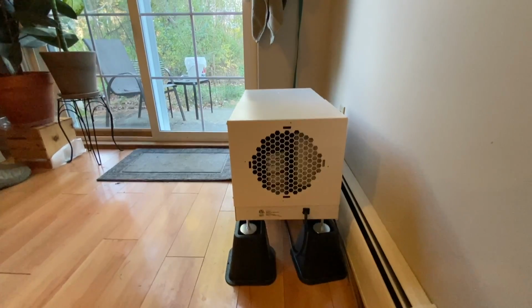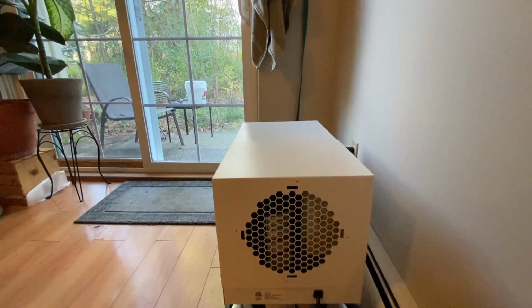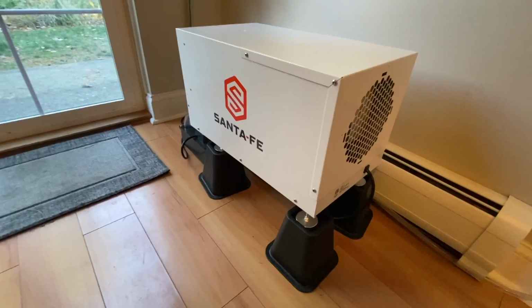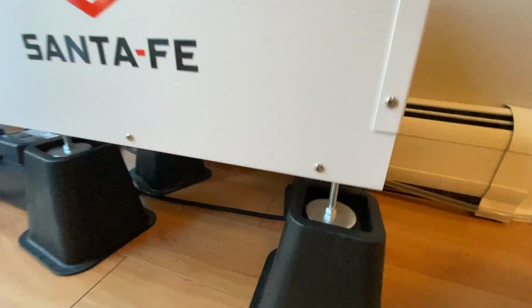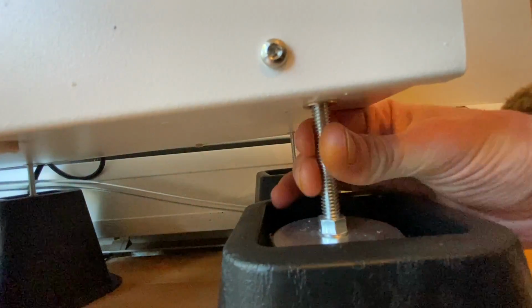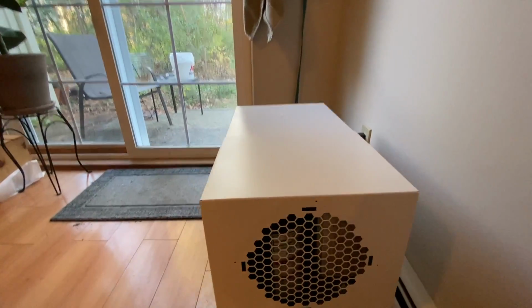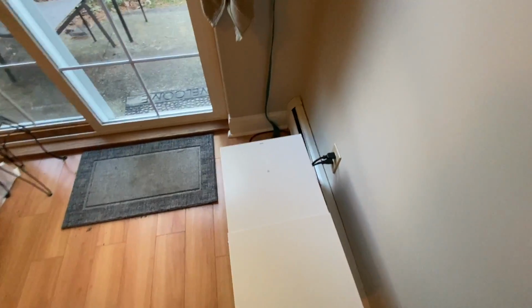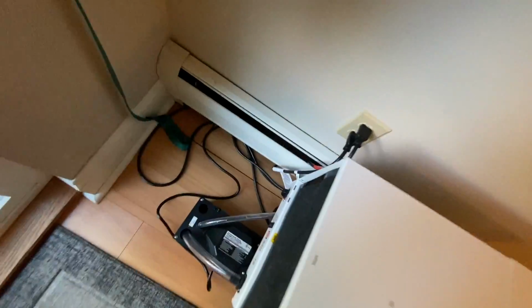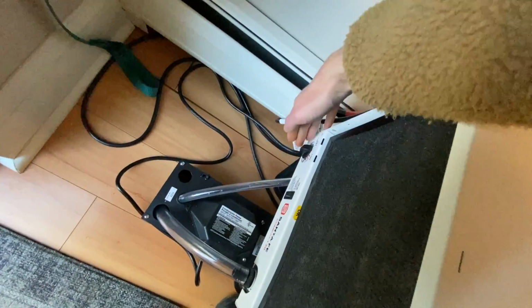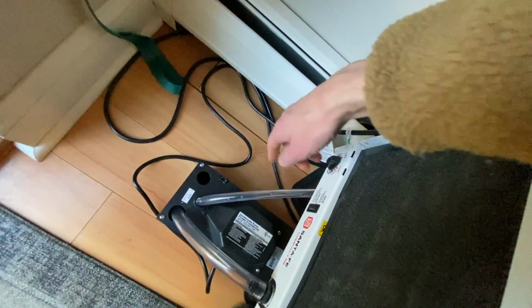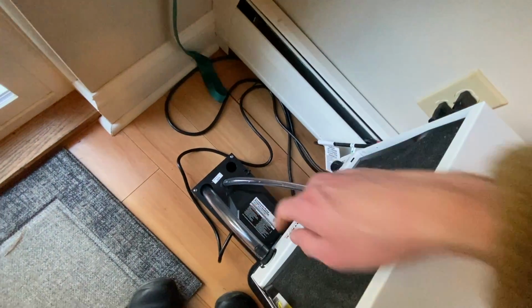After you've situated it on risers, what you're going to do then is level it. And the way that you're going to accomplish leveling it is you're going to be tightening or loosening these legs. So depending on which way you screw them, they can become shorter or longer. Leveling your dehumidifier is extremely important, so do not skip this step, because if you do, you could have water pooling in the bottom of your machine and leaking out of here instead of draining into the pump, which I'll show you how to set up later.